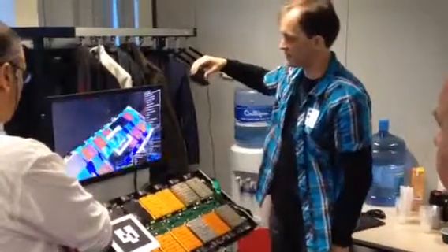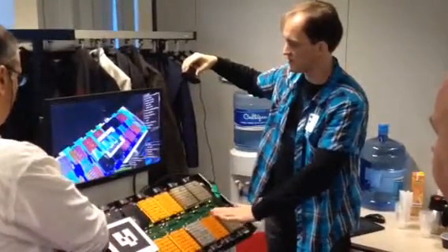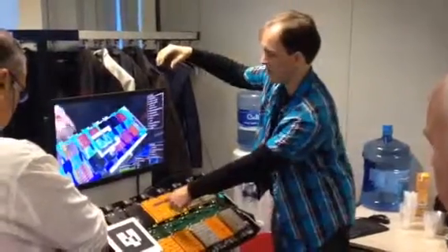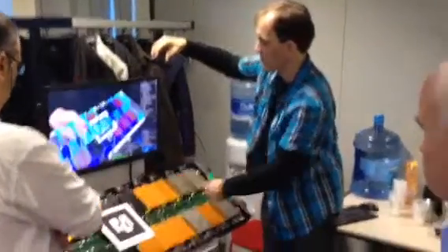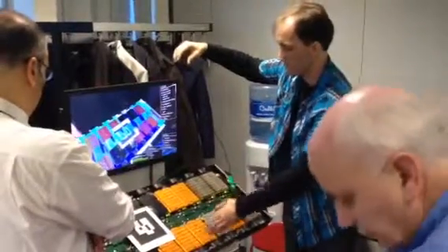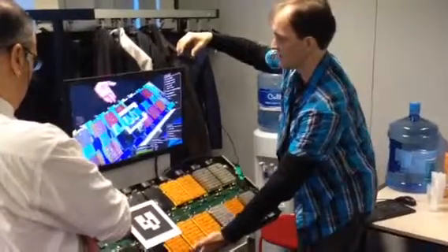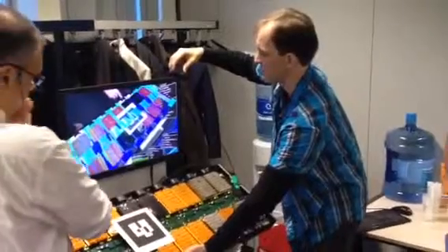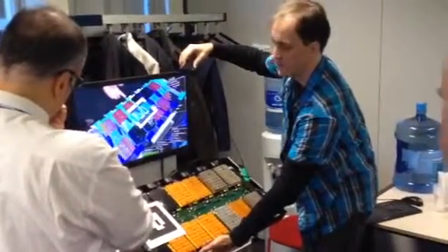If I look at this again, you now see color on a cutting surface through the system representing the temperatures. So you clearly see that these nodes here are hotter. They create more heat, so the air warms up, and this also reflects here at these outlets. While you see a good difference between the temperature on this node here, on this exit, this is even higher than the one here, right?